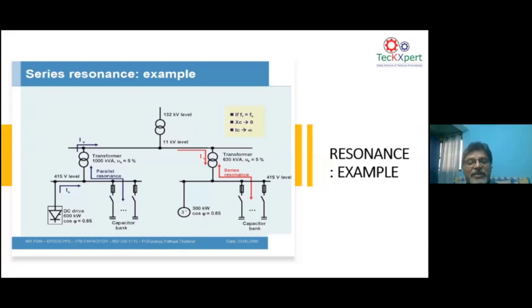The series resonance, what you can see here is, in a parallel resonance, the source is all sitting on one network. In a series resonance, you can see the source of nonlinear load is elsewhere. That means if your factory is connected to a grid, and the grid is, let's say, having only linear loads. You have a motor, then you have fixed capacitors or automatic capacitors. Now, you will sometimes have this capacitor bank failing because of series resonance, because the grid is bringing harmonic current either from a neighboring factory, or the grid itself may have harmonics which will come here and cause a series resonance. That means whenever you put a capacitor network, you will either have a problem with a series resonance or a parallel resonance.